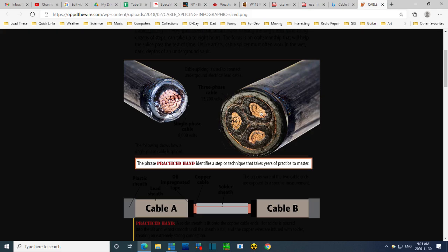Now they jam lots of little fillers. There's some filler stuff in here, but before Mr. Hochstädter came along in about 1927, maybe, all these types of cables went in without this shield. And when I was working at Toronto Hydro, we were pulling out cables that had blown and were that vintage from the 1920s, been operating for, at that time, 60 years. And they always failed right in the middle here with a huge explosion.